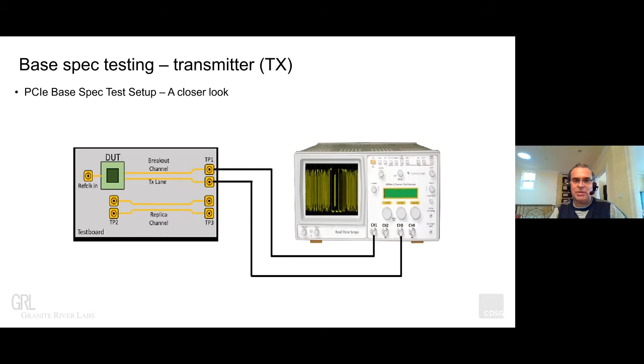So those test fixtures are Gen 4 fixtures. I didn't show the Gen 3 ones, but during our video you're going to see how Gen 3 fixtures look. You can see that the test fixture actually consists of 2 CLB boards - that's the first picture, towards the center of the slide. One of them is by 1 and by 16 type of topology, and the second one is by 4 by 8. Right in the middle, the picture is the CBB, which stands for compliance base board.